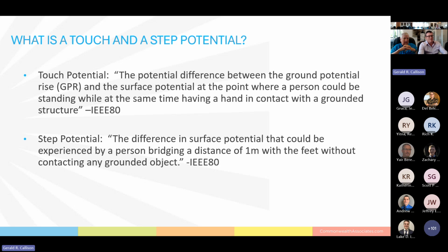Well, I've thrown around the terms touch and step voltage, and it's important to understand what these really are when we're understanding grounding. So we'll look at the standard definitions. Touch potential is the difference between the ground potential rise, the GPR, and the surface potential at the point where a person could be standing while at the same time having a hand in contact with a grounded structure. A step potential is the difference in surface potential that could be experienced by a person bridging a distance of 1 meter with the feet without contacting any grounded object.